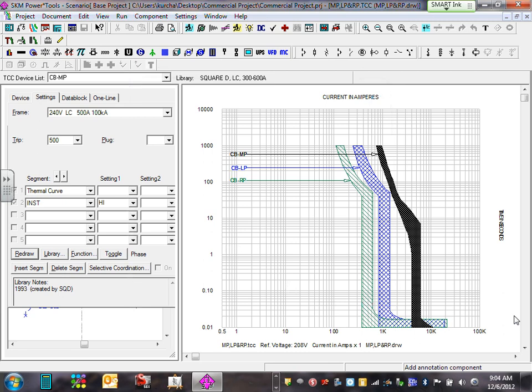Did yours work when you shifted them? No, literally my lines, the 3 lines are stopping at just above 1K. That's a short circuit issue. That's your short circuit calculation. The value that you guys can see right here is the largest amount of short circuit that you encounter in your system. This value here is set by the largest short circuit inside your panels. Okay, that's your calculation. When we adjust the loads in yours, it shifted it.